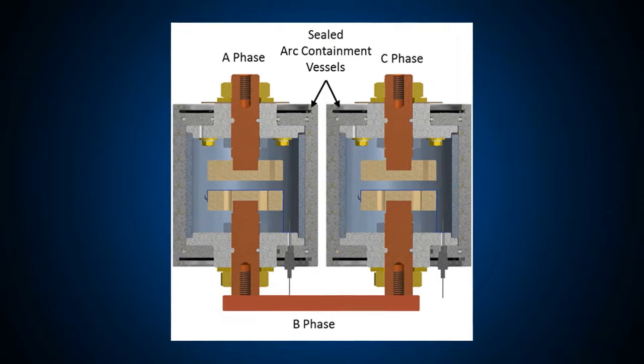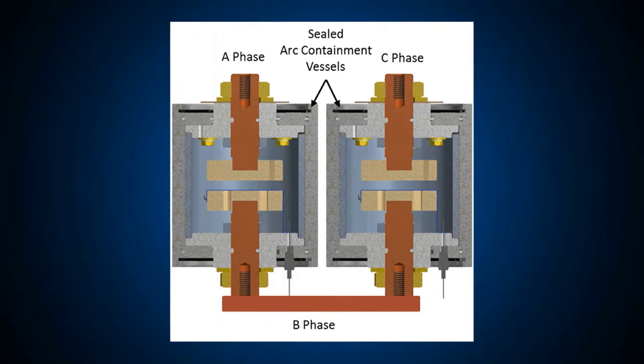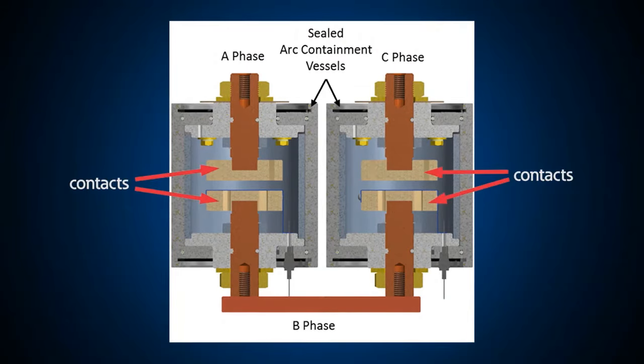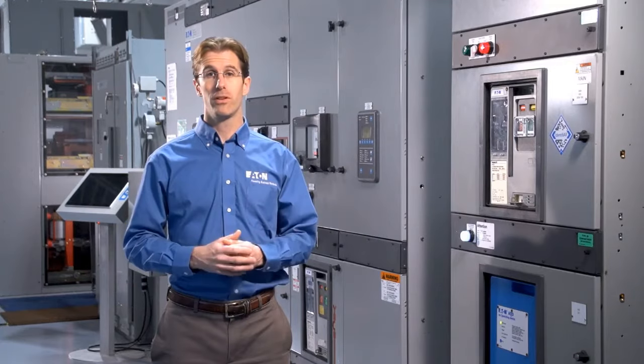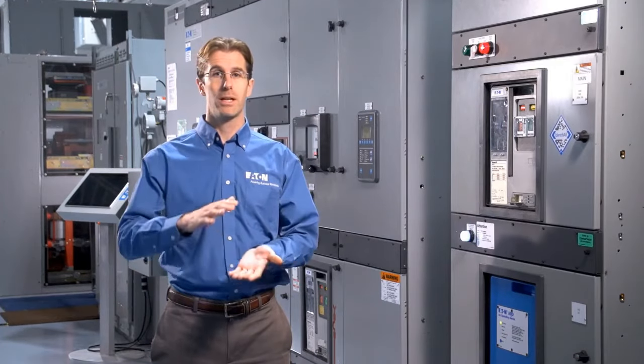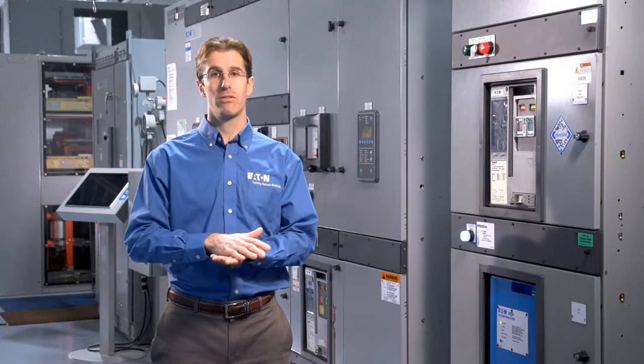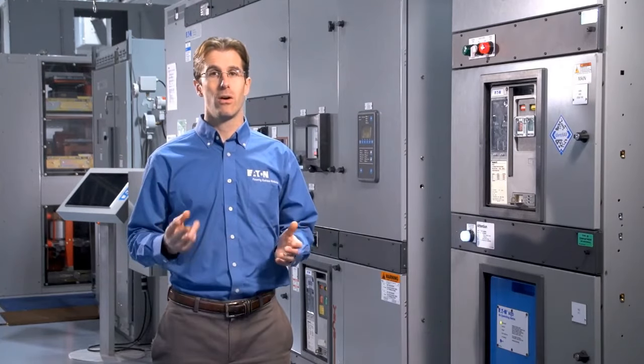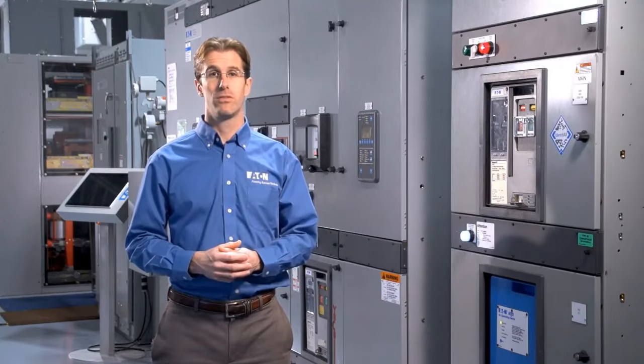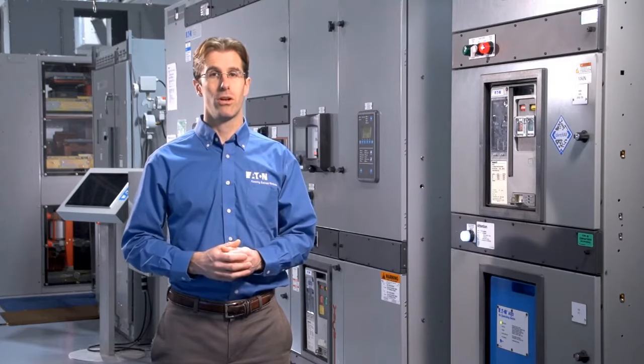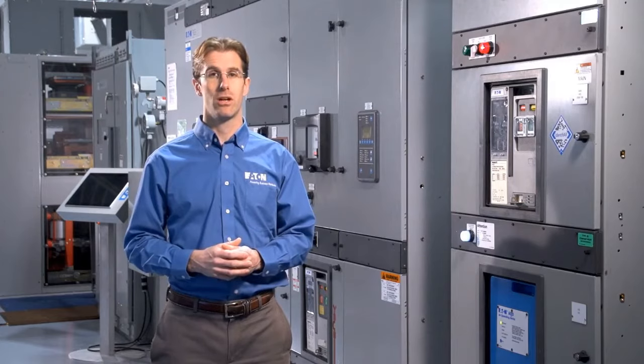You'll notice at the top of the left vessel, we connect phase A. At the top of the right vessel, we connect phase C. And to the bottom of both vessels, we connect phase B. And each of the phases is connected to contacts, shown in tan on this diagram. If this were a bolted fault device, one way to make it work would be to clap the contacts together whenever an arcing fault is detected. This would tie all 3 phases together in a zero impedance fault, which would divert all of the current from the arcing fault into this device, immediately extinguishing the arcing fault.